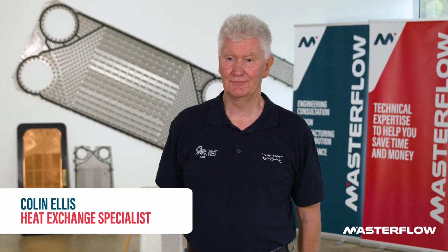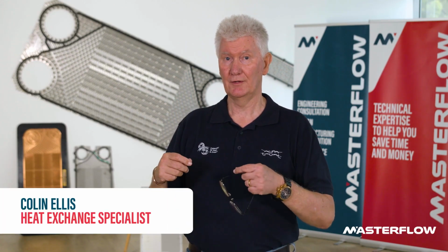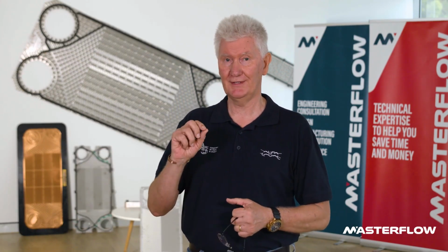The selection of plate material really depends upon the quality of water you want to pass through the heat exchanger and the operating temperatures. There's been a tendency in the market to push more 304. Now 304 does not have any molybdenum content, so its resistance to chlorides is fairly low. You can use it on heating water, you can use it on pools, but your life cycle is actually short.